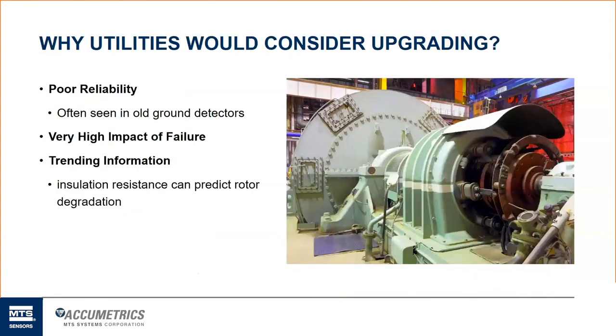So why would utilities consider upgrading to the AFM system? We've harped on this quite a bit, but it's really just the poor reliability. It's very hard to get serviceable items from these old ground detection systems. They've been in service for 60 or 70 years. They have a very high impact failure, and that doesn't give them confidence that their machine is being monitored properly.